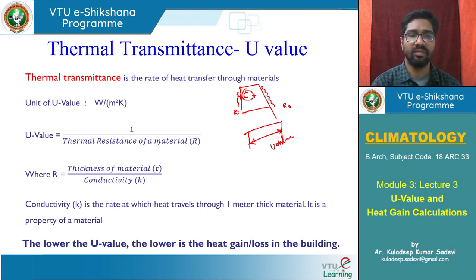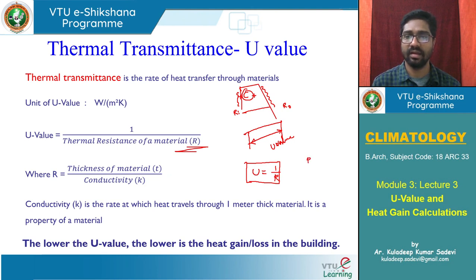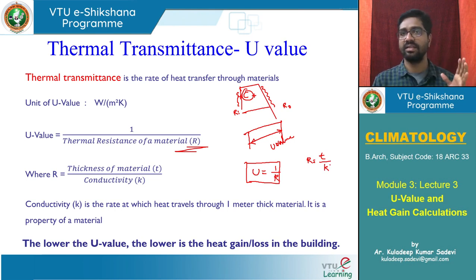U-value is 1 divided by thermal resistance R: U = 1/R. Remember this well — U equals 1 divided by R. For conduction, R depends on conductivity; specifically R equals thickness divided by conductivity. If the material conducts heat transfer very fast, conductivity will be high, meaning resistance will be low. R is directly proportional to thickness and inversely proportional to conductivity.